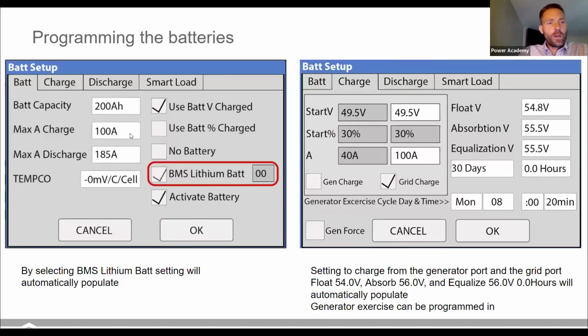Another thing to keep in mind about the max charge and discharge is that this is the global limit. If you have communicating batteries, they might be sending a higher or lower charge. What the Sol-Ark uses is the lower of your setting and the battery setting. The battery has a maximum charge and discharge that it communicates directly to the inverter. If that's above your limit, then it would use your limit here as the global limit. If it's below, then it would use the BMS's value. So that keeps your battery safe. The overall temperature coefficient for lithium batteries should be 0. Their voltage versus state of charge curve doesn't change much with temperature.